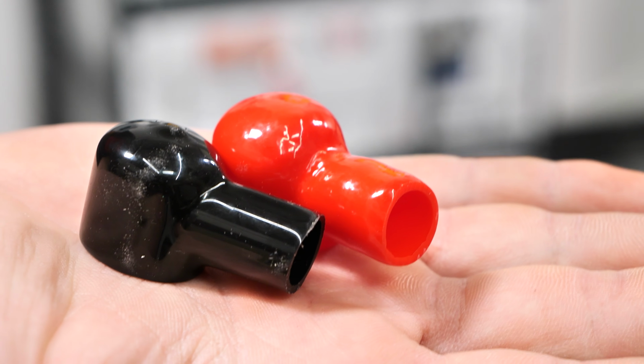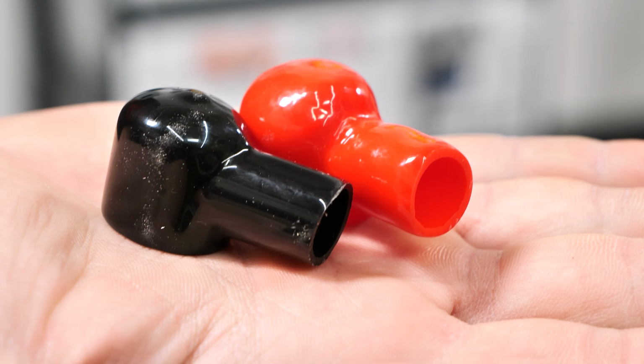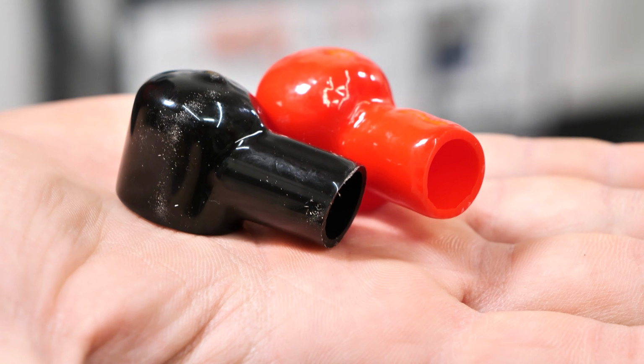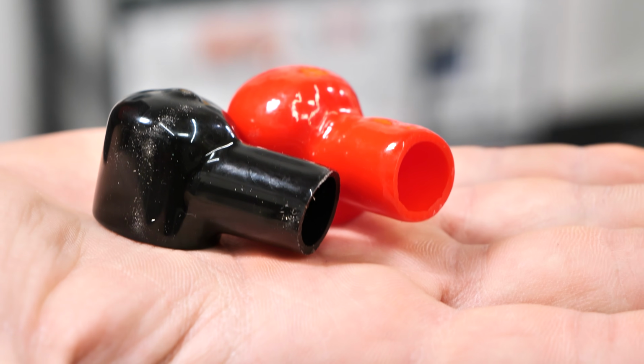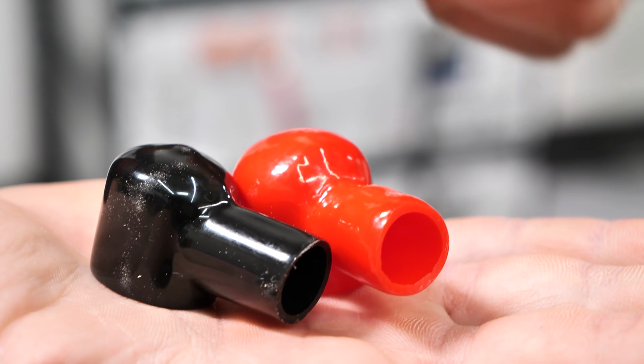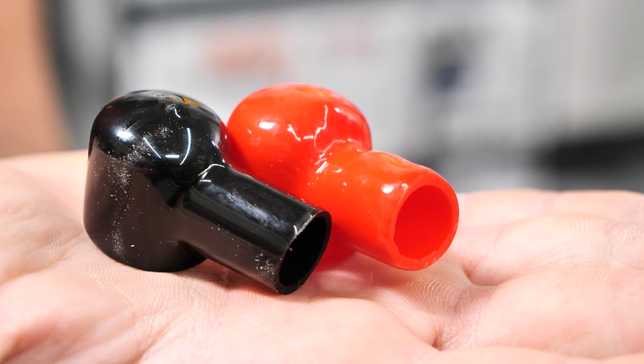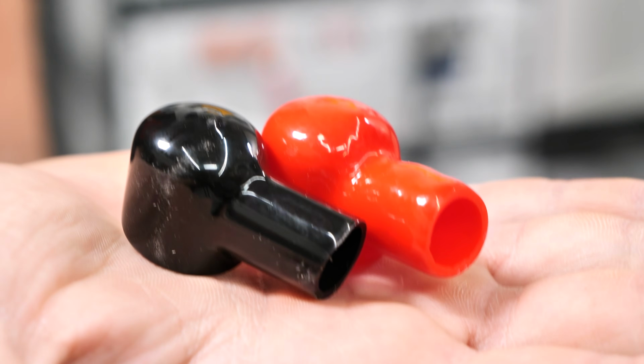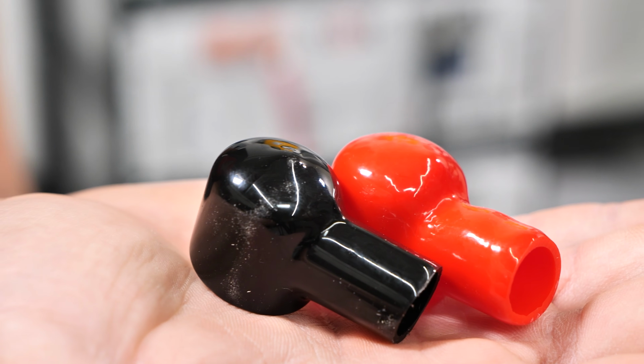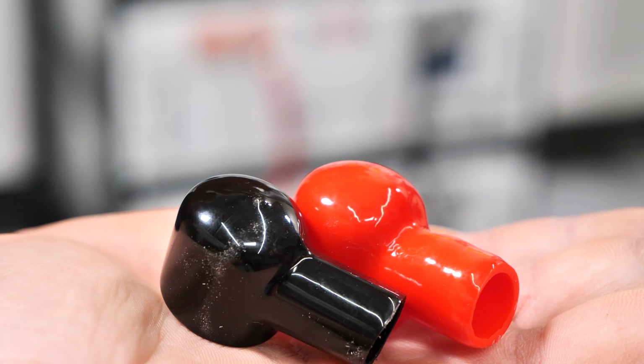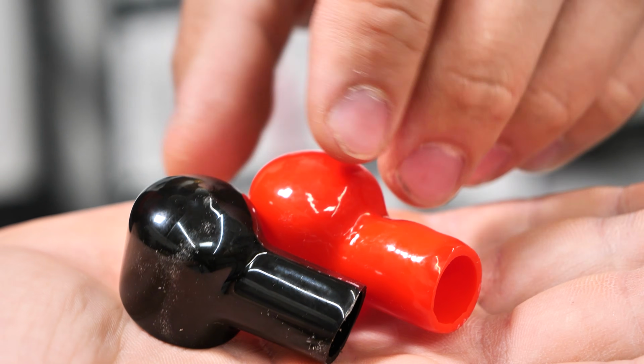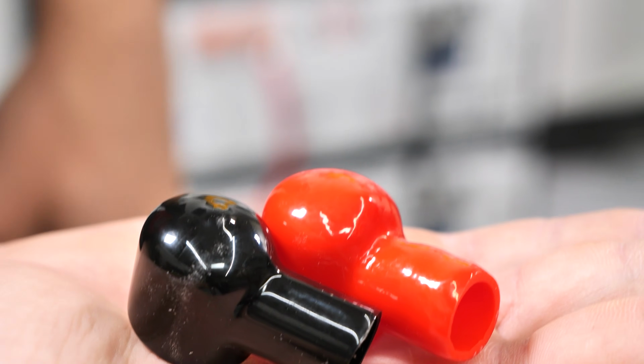Now, these batteries do come with terminal protectors. However, these max out at 2-gauge wire. So for the 2/0 wire I'm using today, they wouldn't be big enough. Essentially, this hole here on the side is not big enough to stick the wire through. So I'm going to be omitting them today, but if you were using 2-gauge wire, these are included with the battery. You can feed your wire through, bend it back, and then put your screw in.